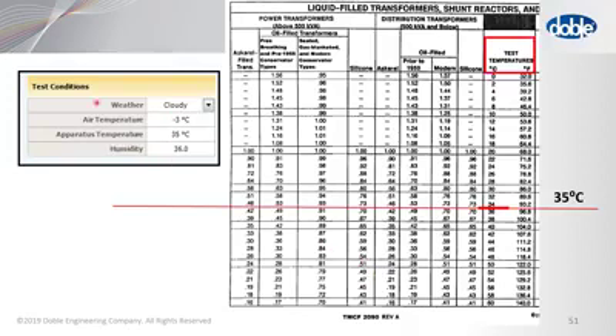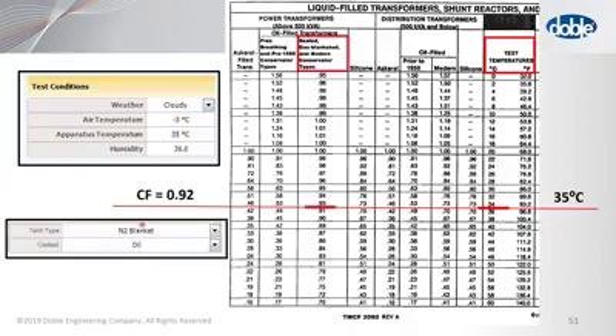Now, as I mentioned, for the particular test that I just showed you, the apparatus temperature, this is the top oil temperature, was 35 degrees C. So that on the chart is right there. There's the 35 degrees C. Now, it doesn't make a difference what the air temperature is. It's the apparatus temperature we want, because the air temperature doesn't affect the overall test that much. It could actually be below freezing, and you still get representative tests. And then, of course, the tank type that was chosen by the person doing the test is nitrogen blanketed, and it's an oil coolant. So that's the oil filled. It's a power transformer, by the way, and it's gas blanketed, and that's how you get that value of 0.92. It's right out of the chart.